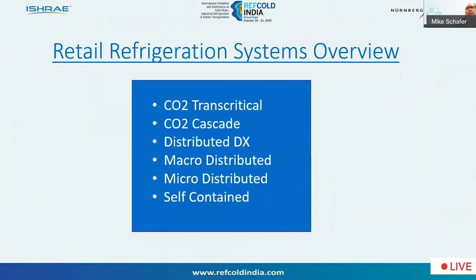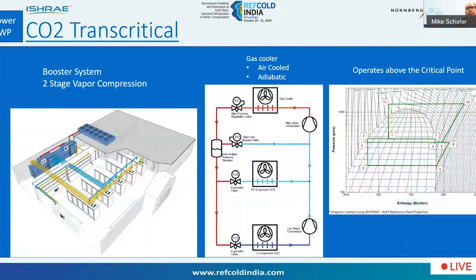So what are the refrigeration systems? We're going to go ahead and look at these systems, as I mentioned before, in the agenda. We'll start with CO2 Transcritical. So from a strategy perspective, this is clearly lowering the GWP. The system is characterized by 2 stages of compression. This would be a simple booster system, which by definition, the transcritical system is going to operate above the critical point of the refrigerant for some period of time during the year.